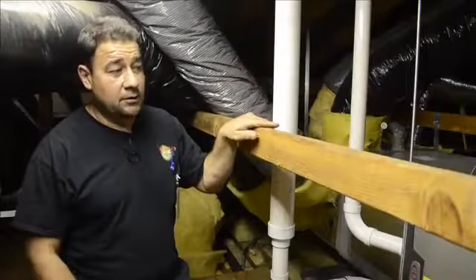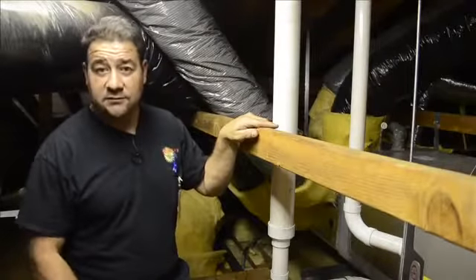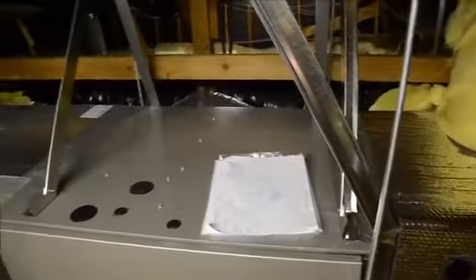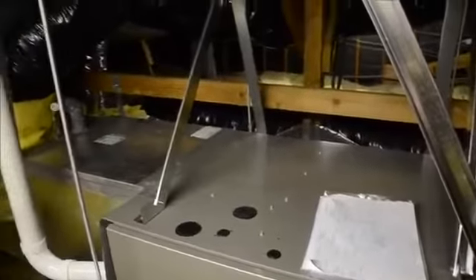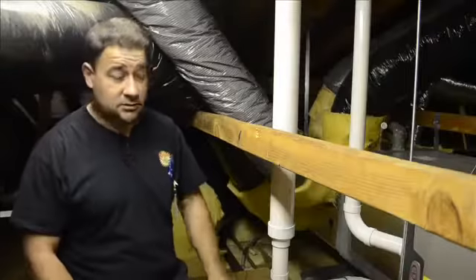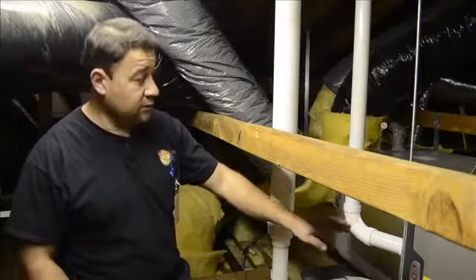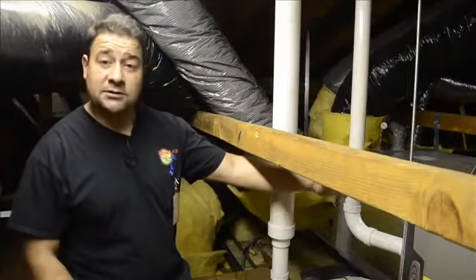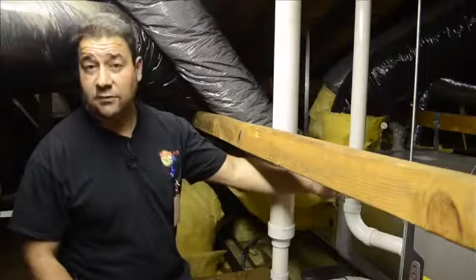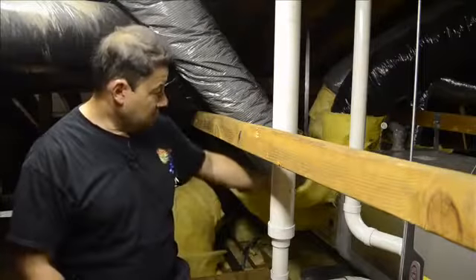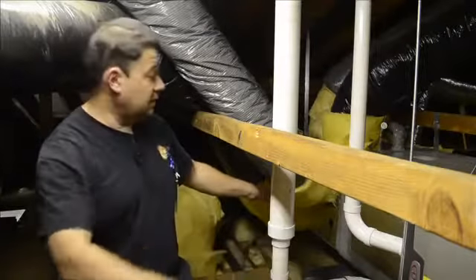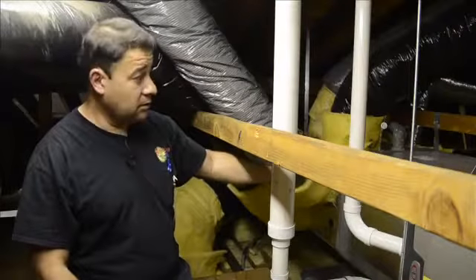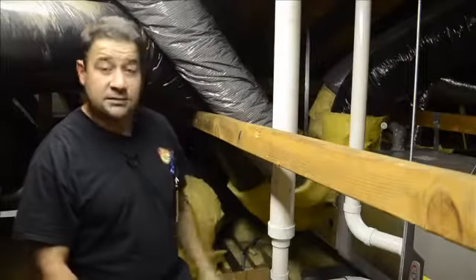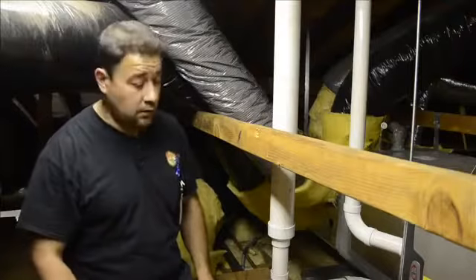Today we're looking at the brand new installation, completed installation that is, of the Lennox EL296V variable speed 2-stage 96% efficiency furnace. Earlier in the video you saw the old piece of equipment in the customer's attic. This is the new furnace with the new supply coil with the factory installed TXV or TEV valve, thermostatic expansion valve, accompanied by two new plenums, sealed to the old existing ductwork on everything. We have a sight glass there for proper refrigerant charge as well.